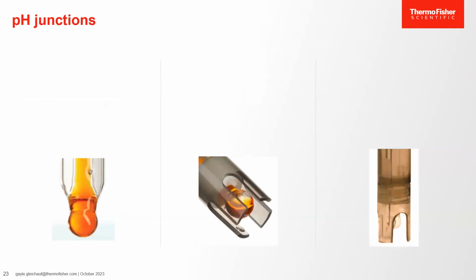pH electrodes come with a choice of junction styles. You may not know it, but the junction style is closely associated with the performance of the electrode, such as the speed, stability, and lifetime. The junction is generally a porous substance that sits between the pH electrode reference solution and the sample. It enables the necessary electrical connection between the reference electrode and the sample. If the junction doesn't work well, the electrode can be slow and drifty. A clogged junction may not work at all. Choosing the right junction makes a difference.